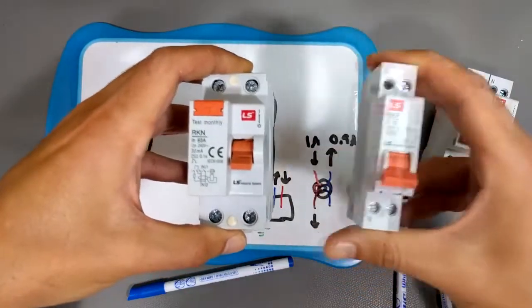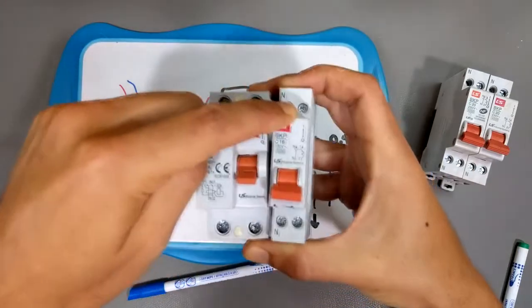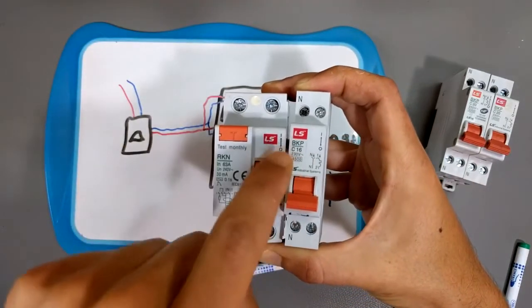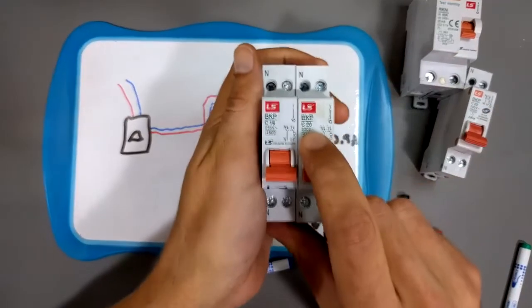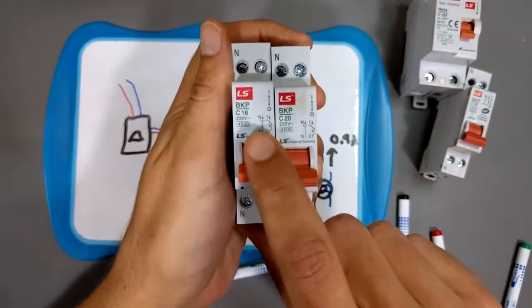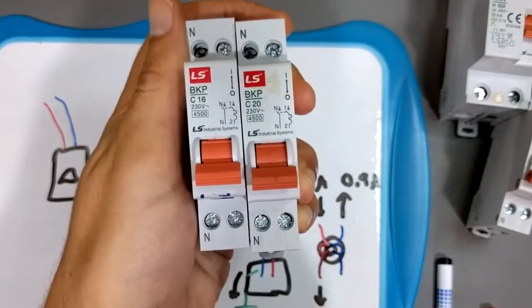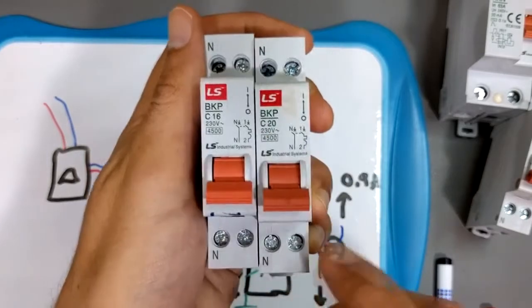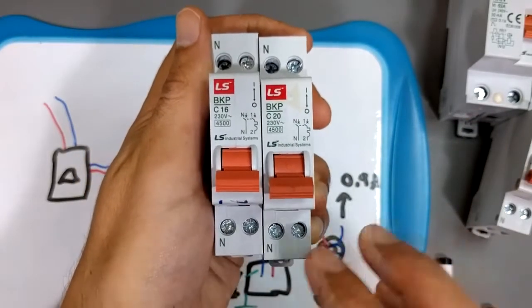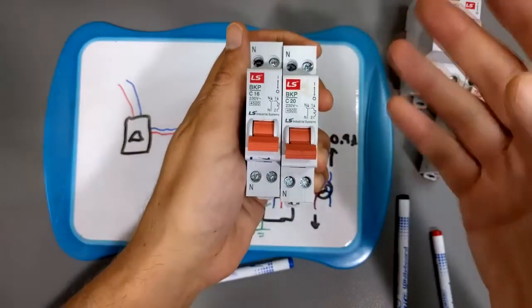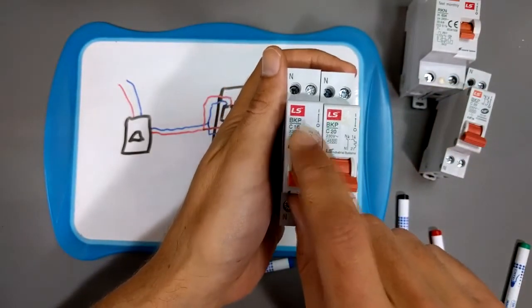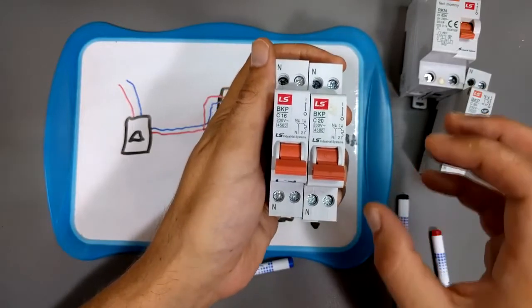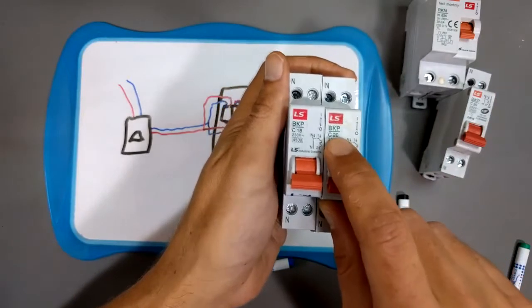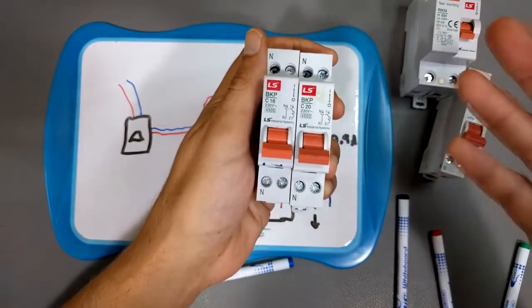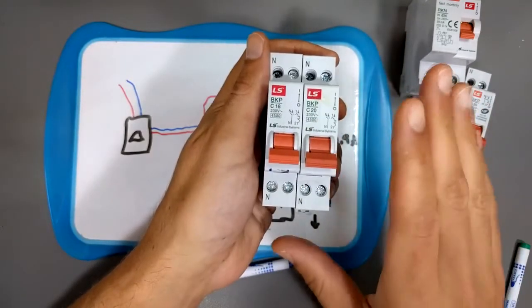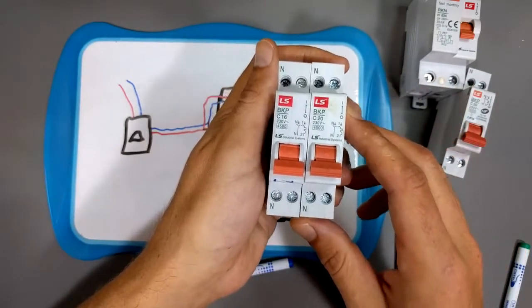And then each one of these protects a whole row of normal thermomagnetic breakers, and the purpose of these guys is strictly to detect overcurrent conditions, because there are also 20 amp breakers, 16 amp, 20 amp. Typically a 16 amp breaker will be associated with a certain diameter of wiring coming out of it, and a 20 amp breaker will usually have fatter, thicker wiring coming out, and you have to use a specific size of wire with a different type of breaker. Depending on where you live, there are certain rules and regulations. If you have a 16 amp breaker, you use such and such gauge wire, and you can only hook up X number of power outlets to it. Whereas if you have a 20 amp breaker, you have to use this diameter of wire, and you can hook up more power outlets to it. Those rules you have to check depending on the country where you live. They're different for every country, and it gets complicated.